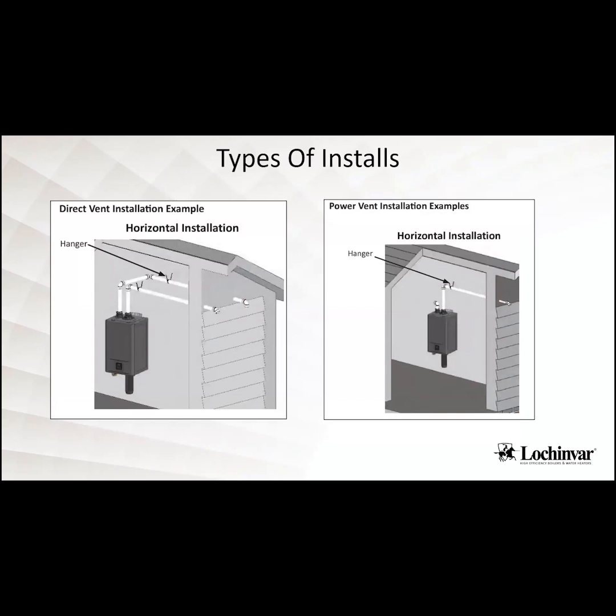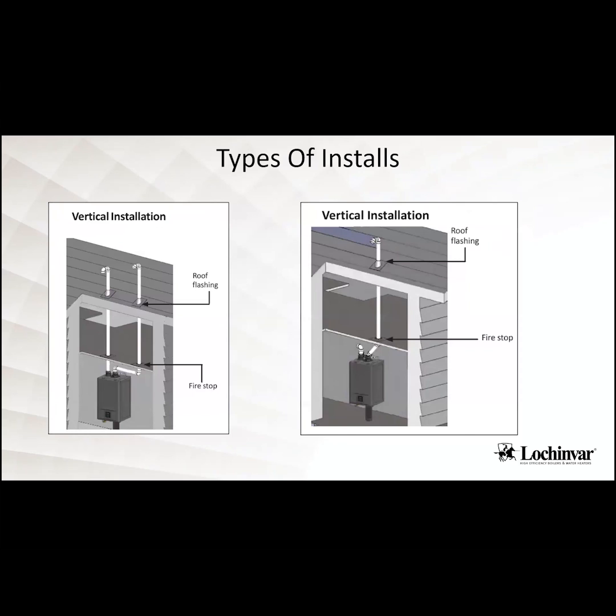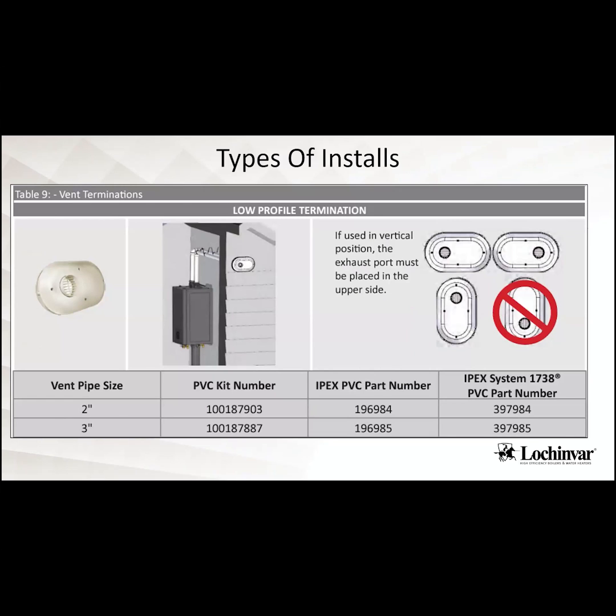All righty. So just types of installs: the horizontal, single pipe, 2 pipe on that unit, going up through the roof with 2 pipes and a single pipe. These are approved for those flat wall terminations, whether it's a 2-inch or a 3-inch IPEX coming out. When these are piped in, just make sure that our exhaust is coming out the exhaust and the intake is coming out the intake. In my years of tankless, I've seen 2 doors blown off of units because they were piped backwards and it was recirculating, and it recirculated enough non-combusted flue gases that it finally blew the actual doors off of those units.